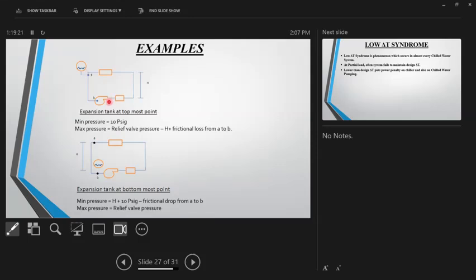It should be this pressure, let's say PN16 minus H, correct? Because that is the reduction. This is the static head which has gone into the system. If the pressure goes over here, I will see the pressure at this point minus the static head. So the maximum pressure in the expansion tank can be PN16 or PN10 minus height, plus say the friction loss from A to B, because the pressure over here should be sufficient to take care of this friction drop, correct? So my maximum pressure in the tank can be PN16 minus H plus the pressure drop from this to this.